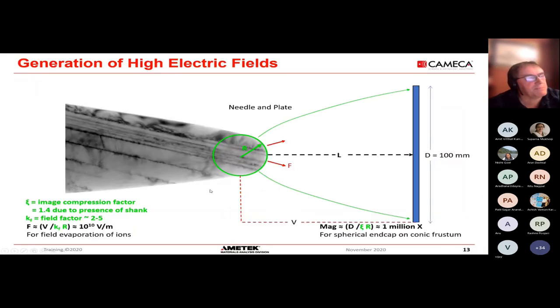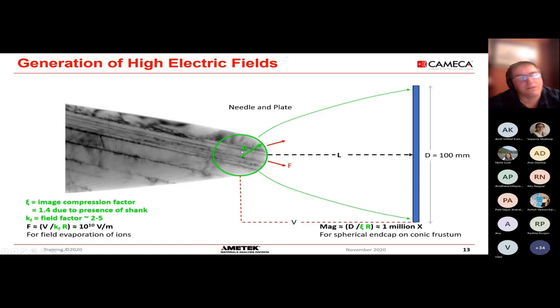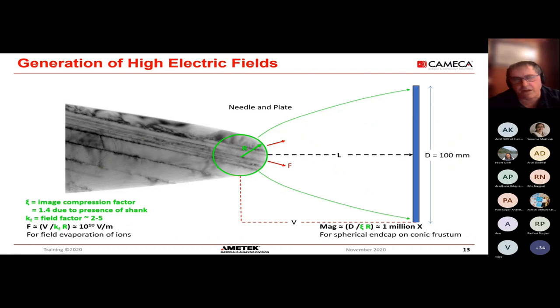The specimen is shaped into the form of a needle with a very sharp tip — a radius of the order of tens or hundreds of nanometers. The technique is a point projection method: when ions leave the surface, they hit our detector. Because our detector is six orders of magnitude bigger than our specimen, we can measure the arrival position carefully enough to infer, using a simple reconstruction algorithm, the departure position of the ion. This is what fundamentally allows the technique to work.